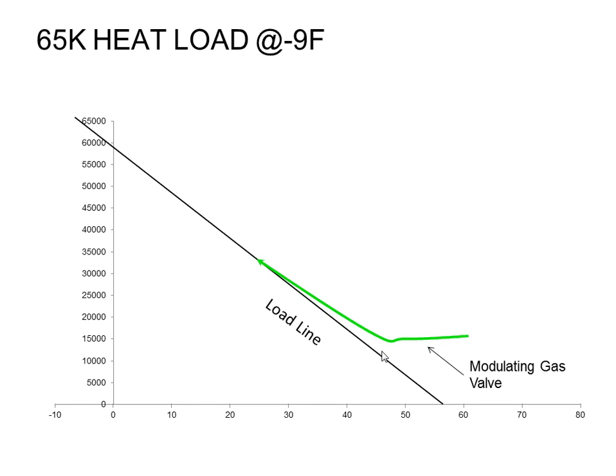So let's say, for example, you had your heat set on 72 degrees, and you walked up to the thermostat and you said, you know what, I don't want it to be 72, I want it to be 69. You bumped the stat down 3 degrees. Well, the furnace is going to recognize that and say, oh, you want it to be 3 degrees cooler in here.